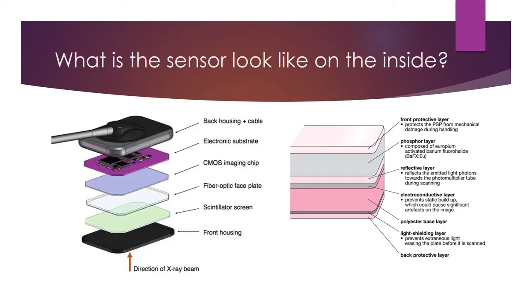Looking at the internal structure: a CMOS or CCD sensor has multiple layers — back housing and cable, an electronic substrate, an imaging chip, a fiber optic face, a scintillating screen, and a front housing where x-rays strike the sensor. A PSP sensor, on the other hand, has a front layer, phosphor layer, reflective layer, electroconductive layer, a polyester base, light shielding, and a back protective layer.